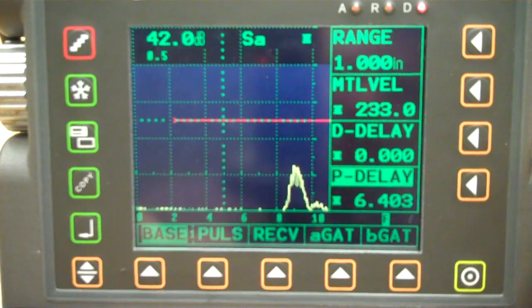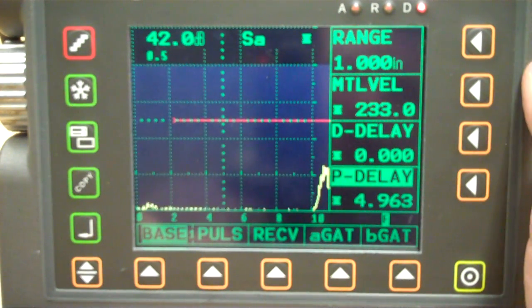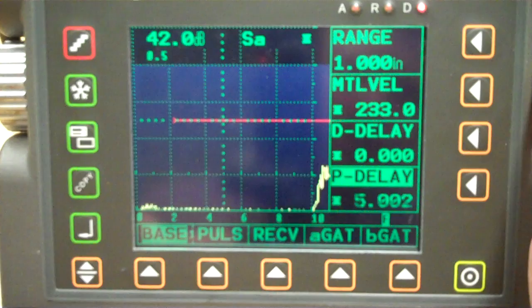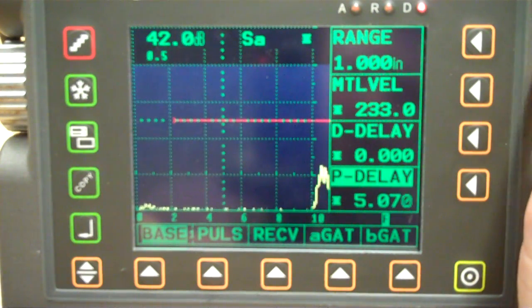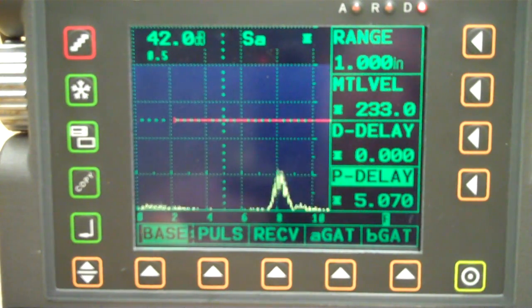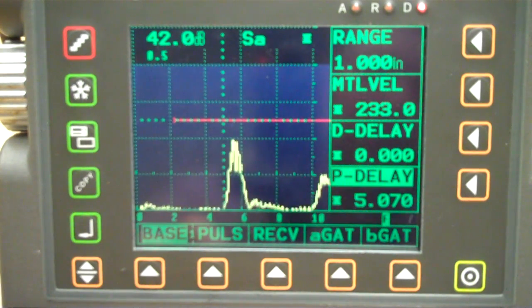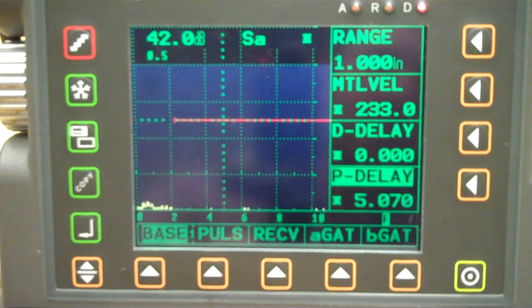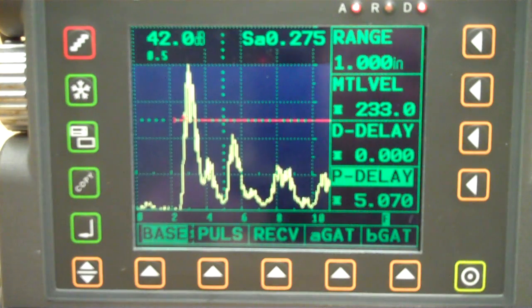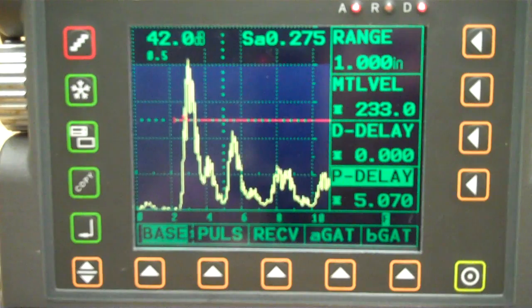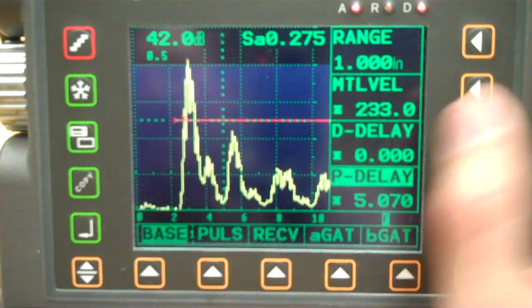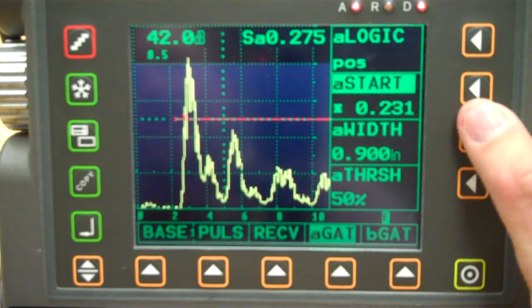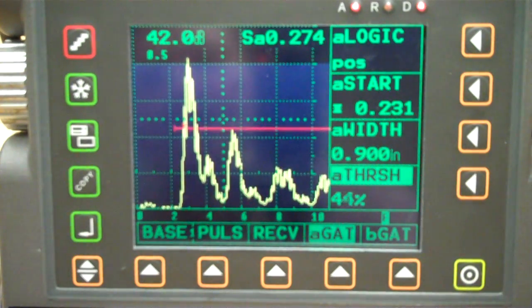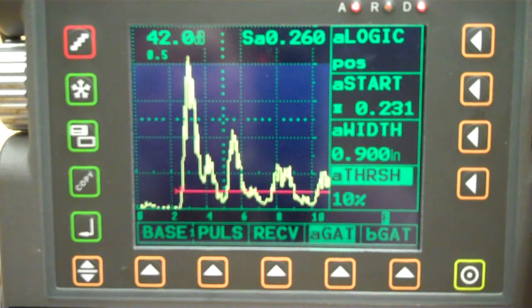So let's just take this thing, drag our delay back over here. Right there, there's 1 inch. There's 3/4 of an inch, which we're not necessarily right on, but we're pretty close. And then there's 25, 50, 75, 100. So you see here, it looks like we've got 275, which is fine. But if we take this gate and bring our threshold of our gate down, you see that number gets smaller and smaller very quickly.